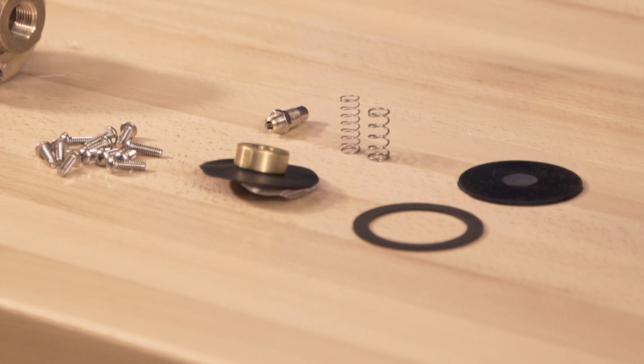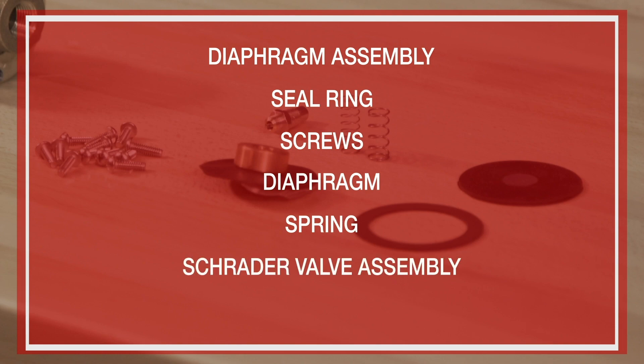We will be covering the installation of the maintenance kit for the Viking Model C1 pressure-operated relief valve. The repair parts offered in the maintenance kit are as follows: diaphragm assembly, seal ring, screws, diaphragm, spring, schrader valve assembly, and the clapper spring.